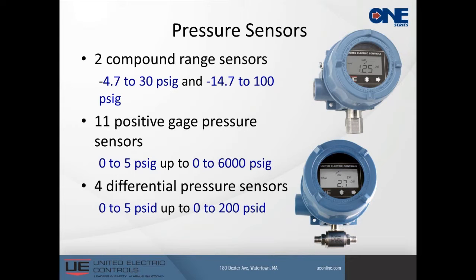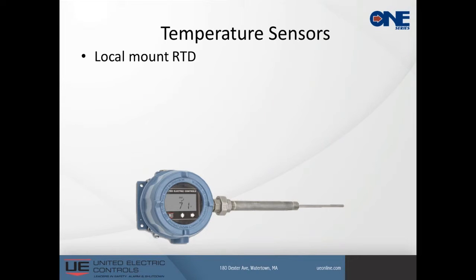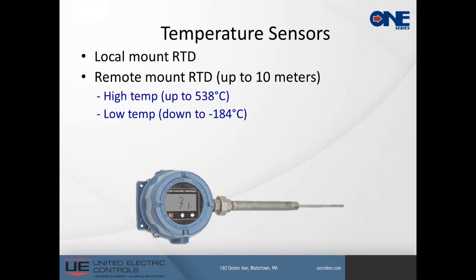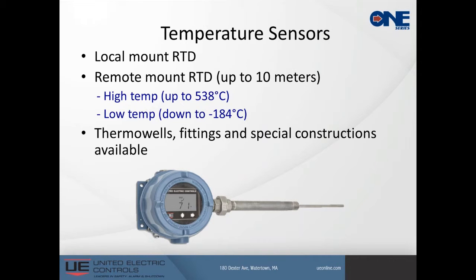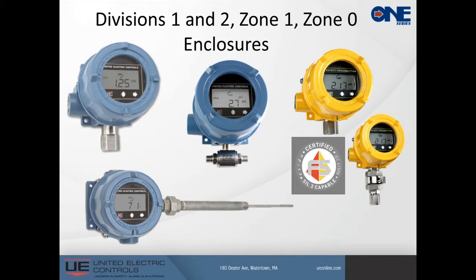And then we have 4 differential pressure sensors available as well. Temperature: these are either local mounted RTDs or remote mount RTDs. They are RTDs simply because this is self-diagnostic, and we can detect should an RTD fail and get that announced back to the HMI quickly. Thermowells, any type of configuration to make this work, we can also make that happen.